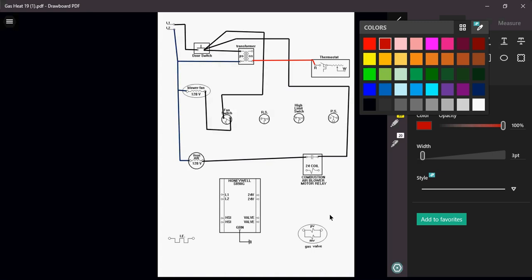What does my rollout switch do? What does my high limit switch do? What does the pressure switch do? Okay, well, the pressure switch is a very important part. Okay, it's just like the name states. It's a pressure switch. It's sensing pressure. Okay, usually your pressure switches are going to be what is going to sense the pressure difference inside your heat exchanger. It's going to tell that furnace whether or not your heat exchanger is clear of any sort of debris, any sort of non-condensable gases. It's going to tell us whether or not the heat exchanger is actually solid or is it cracked.